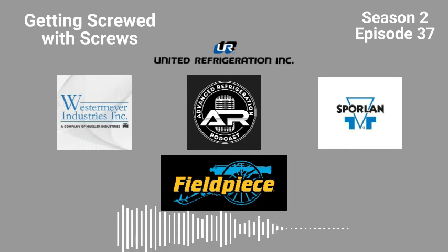I got you. So that was the first sign that these things were broken, and the 6 other service calls for oil failures. Well, you know what? Now that, is this the same rack that had the really shitty oil that was blocking up everything? Yep. I mean, that kind of makes sense, because they both had a block. Both racks had a puck that was broken off. Both had intermediate temp. That's what I'm saying. So basically you're running a really high discharge pressure, an extreme amount of heat in that one compressor, and it's just boiling that oil.